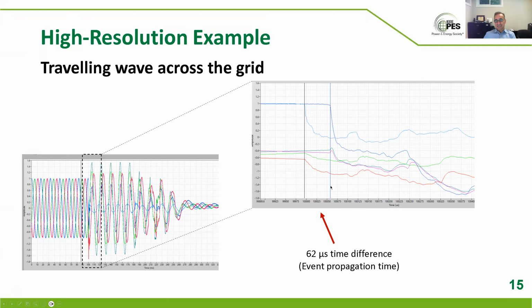So this can give you accurate fault location, but if you sample at the microsecond, you have 300 meters resolution, or when you look at it differentially, 150 meters. So this technique can allow you to locate the fault on a long transmission line within 150 meters or 500 feet, depending on what units you're more comfortable with. That's basically nicely within the tower. That's fairly accurate fault location.